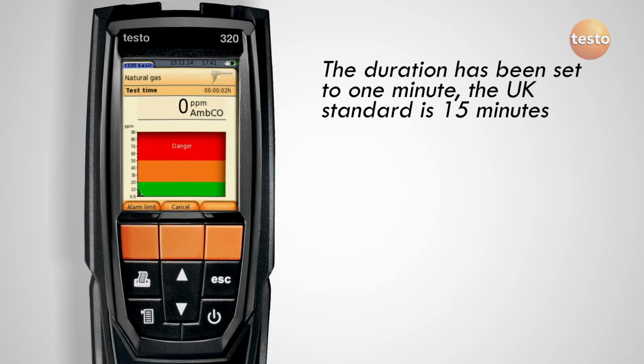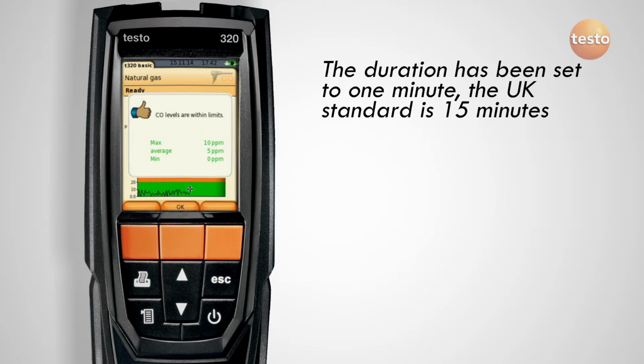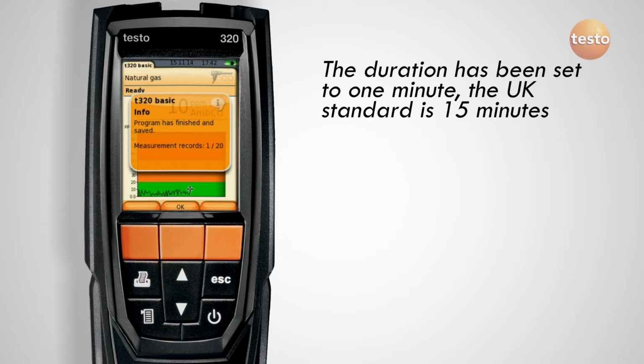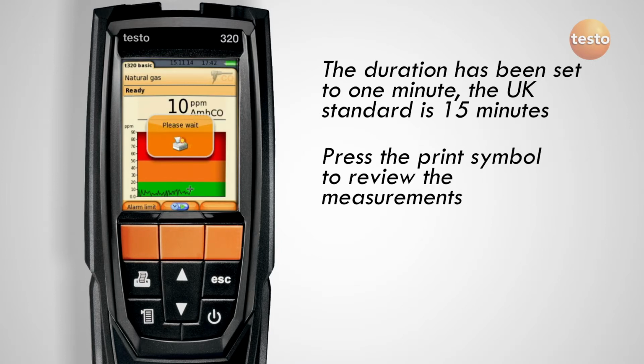At the same time, it charts the CO level against preset warning and alarm limits. If the CO goes above the alarm limit, the analyzer gives an audible alarm, and when the test terminates, it will warn you to switch off the appliances and open the windows. Our test has passed, as indicated by the thumbs up symbol, so now we can print the results.